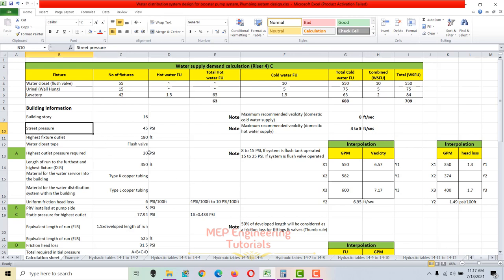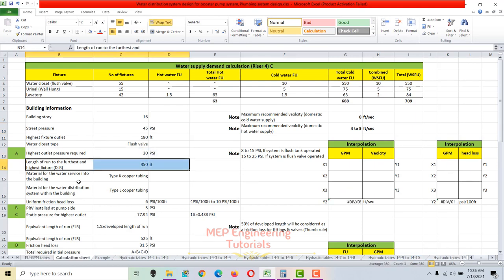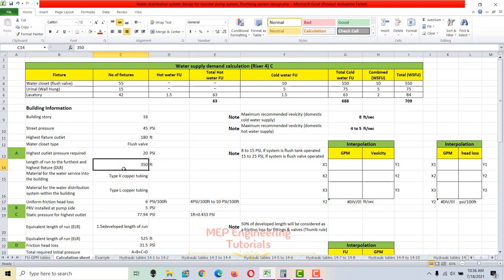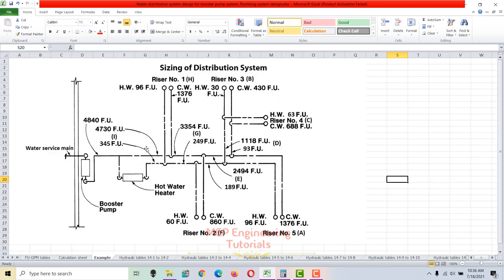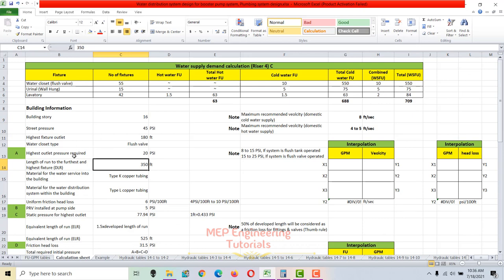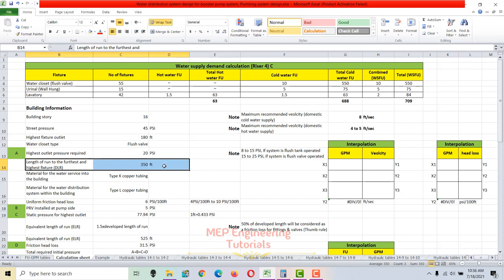Next, we check the length of run to the farthest and highest fixture. You go to your drawing, mark the lengths of each section and riser, and write in that length. Since our water closet is the highest and farthest outlet, we measure up to that point. In this example, the developed length of run (DLR) is 350 feet.